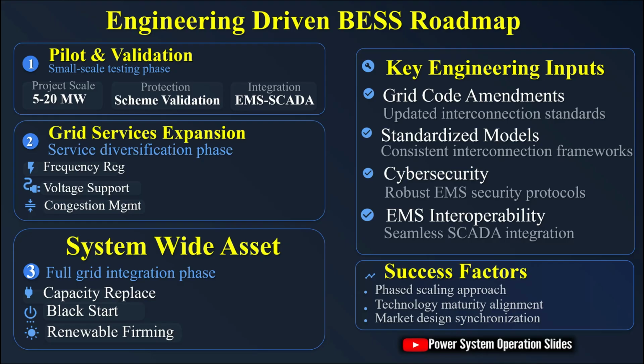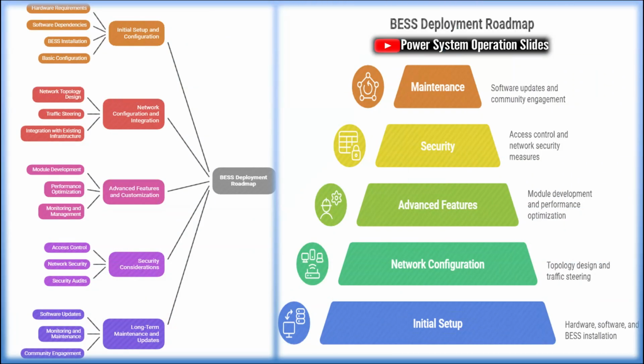Key engineering inputs that must be addressed throughout the roadmap include grid code amendments that recognize BESS capabilities and define technical requirements, standardized interconnection models that streamline the connection process, cybersecurity measures that ensure the secure operation of BESS control systems, and EMS interoperability standards that enable seamless communication between BESS controllers and grid control systems. China State Grid provides a compelling example of a successful BESS deployment roadmap.